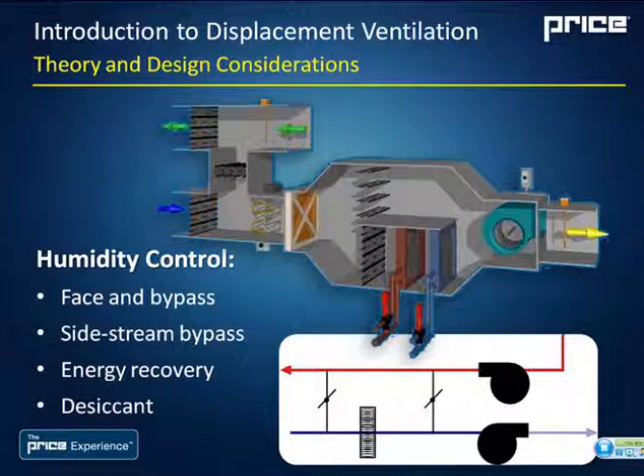I mentioned humidity a little bit in dew point temperature control. Humidity control is still necessary, and of course with a warmer supply temperature, if you're pulling in 65 or 68 degree air, in some cases that just isn't dehumidified enough, so further dehumidification is necessary. Now there are control strategies that will allow you to chill down to 55 and reheat back up to 65 without wasting a significant amount of energy.